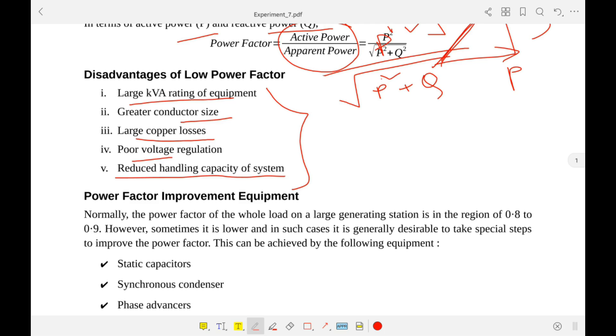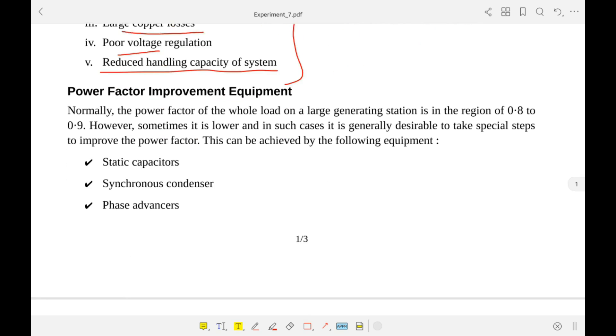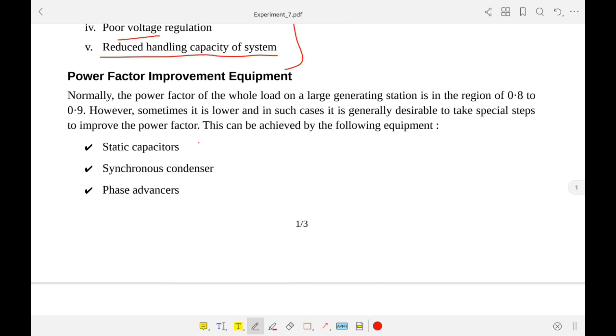Now, the power factor improvement equipment. There are different techniques to increase the power factor. Among these, static capacitors or capacitor banks is one of the most important, and we will be demonstrating this method. There are also synchronous condensers — also called synchronous capacitors — which are synchronous generators that, when overexcited, supply reactive power.